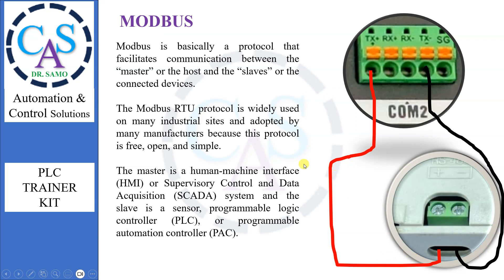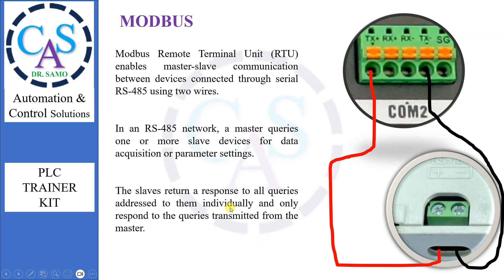Modbus is basically a protocol that facilitates communication between the master or host and the slaves or connected devices. The Modbus RTU protocol is widely used on many industrial sites and adopted by many manufacturers because this protocol is free, open, and simple. The master is a Human Machine Interface, HMI, or Supervisory Control and Data Acquisition, SCADA, system, and the slave is a sensor, Programmable Logic Controller, PLC, or Programmable Automation Controller, PAC. Modbus Remote Terminal Unit, RTU, enables master-slave communication between devices connected through serial RS-485 using two wires. In an RS-485 network, a master queries one or more slave devices for data acquisition or parameter settings. The slaves return a response to all queries addressed to them individually and only respond to queries transmitted from the master.